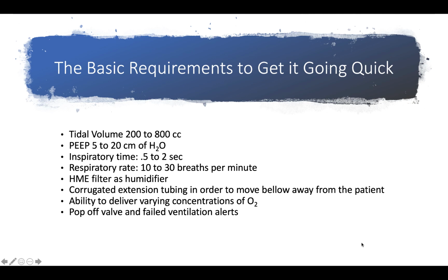The HME filter will not only humidify but also act as an efficient bacterial and viral filter and can be attached between the endotracheal tube and the ambu valve. As alluded to earlier, the corrugated extension tubing is inserted to move the ventilatory bellows a convenient distance away from the patient. The ability to deliver varying concentration of oxygen is a pre-configured element of the ambu apparatus. No ventilator is complete without having a high inspiratory pressure pop-off device and an alarm along with a failed ventilation alert mechanism. They are a must.